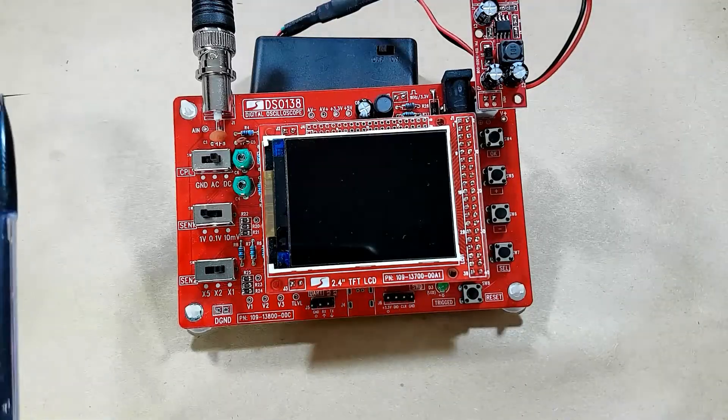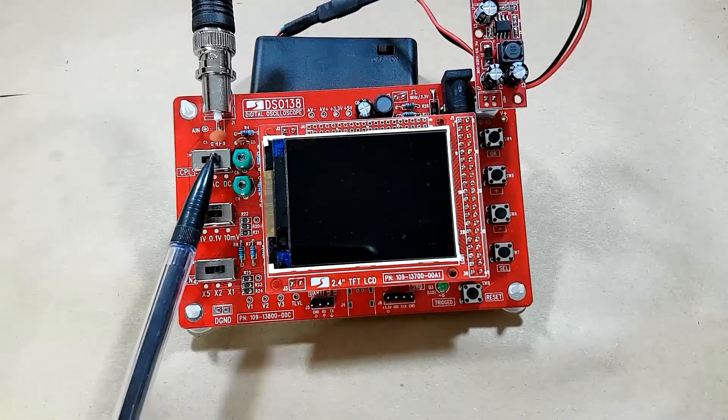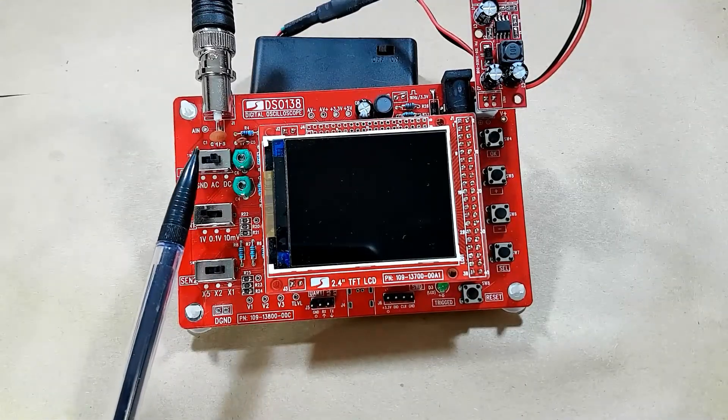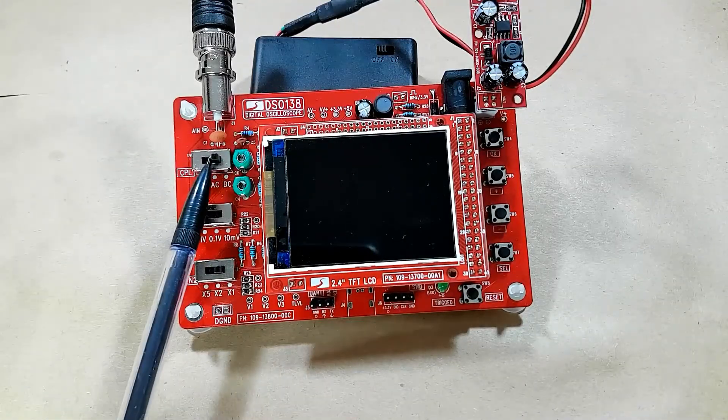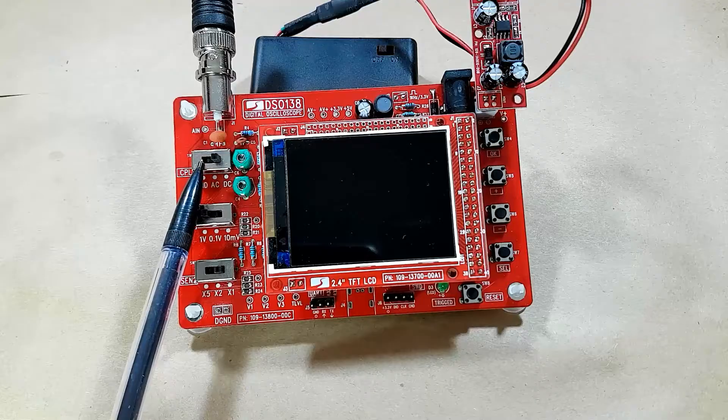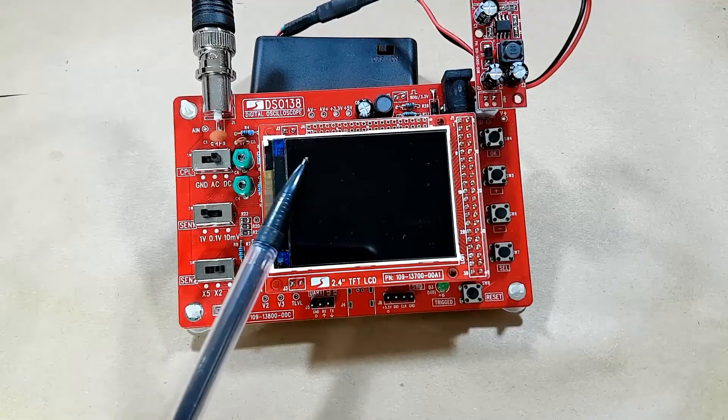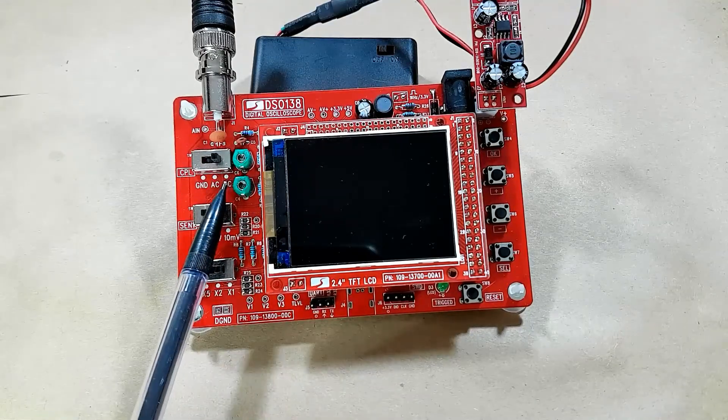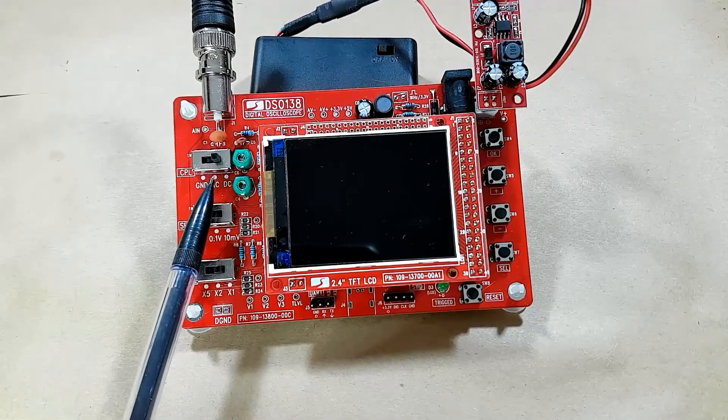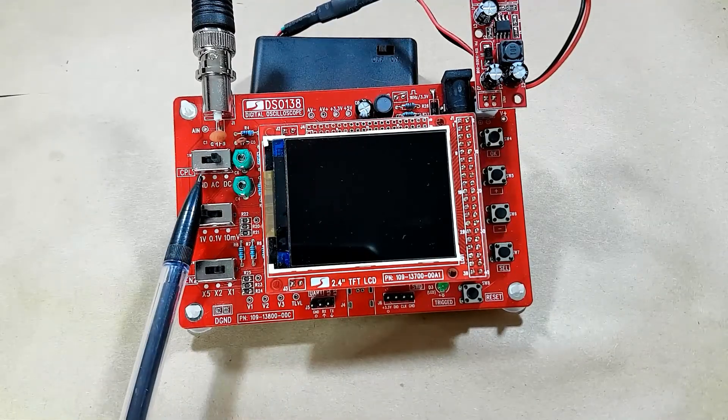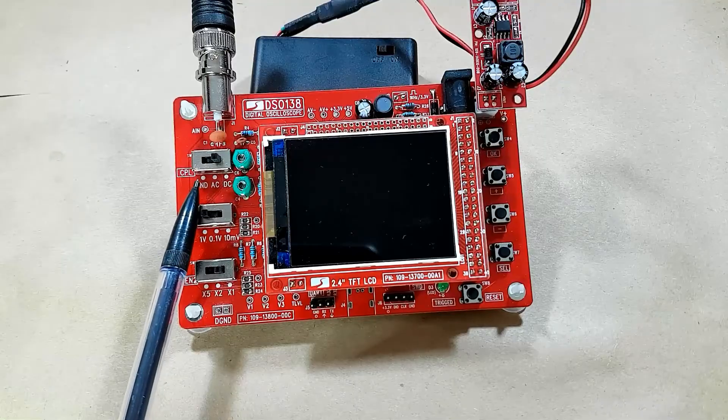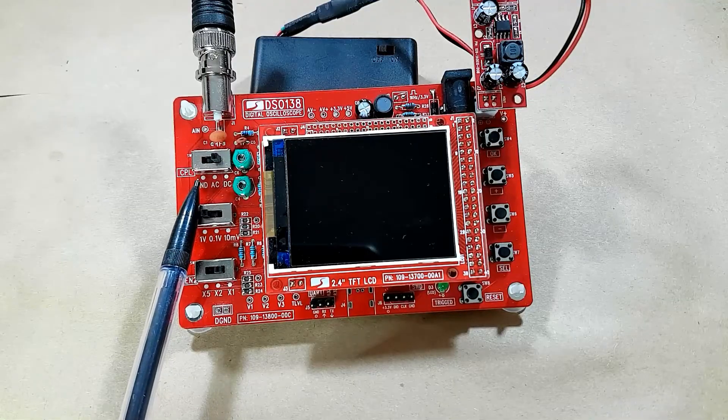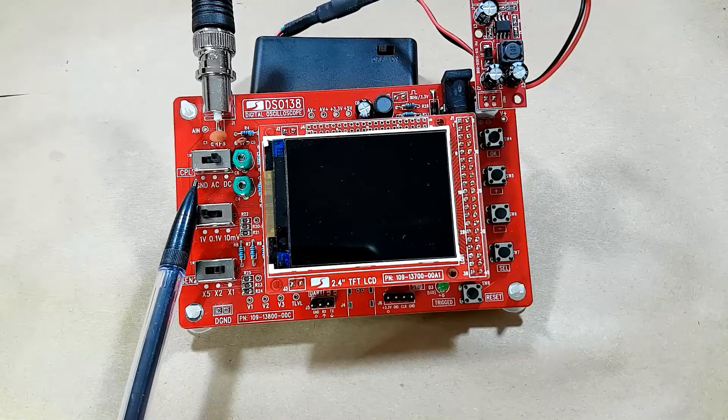Next up, we have the switches on the left side. This is the coupling switch, so this is where you set whether you're measuring DC, AC, or if you want to isolate the input completely, you switch it to ground.